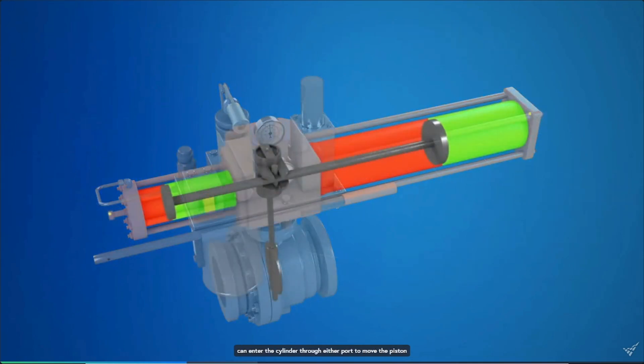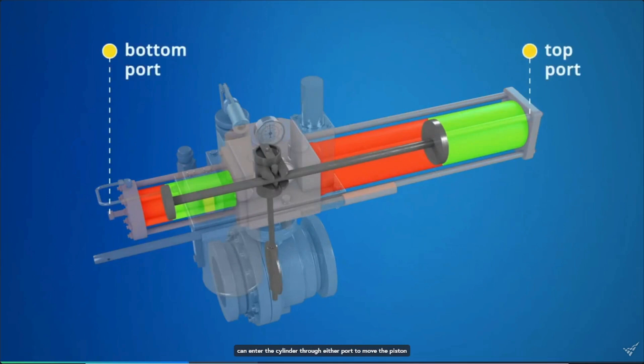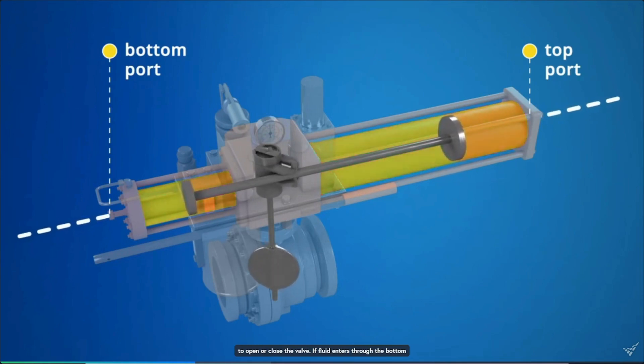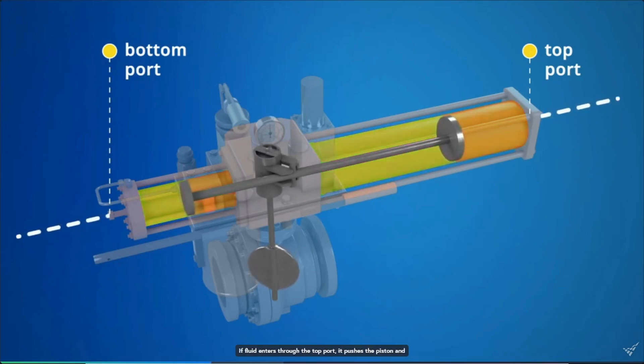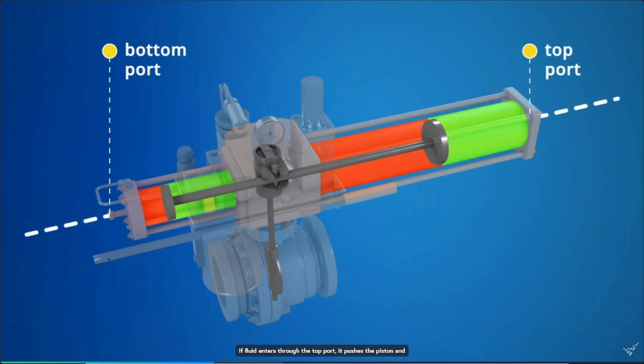Fluid can enter the cylinder through either port to move the piston to open or close the valve. If fluid enters through the bottom port, the piston and piston rod move and open the valve. At the same time, an equal volume of fluid flows out the top port. If fluid enters through the top port, it pushes the piston and piston rod in the opposite direction, closing the valve. An equal volume of fluid is bled through the port at the base of the cylinder.